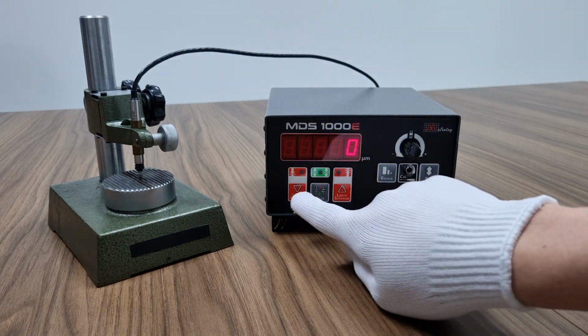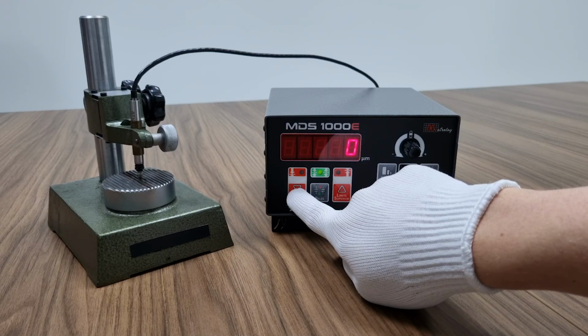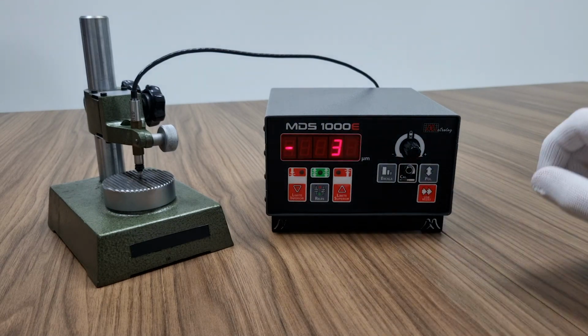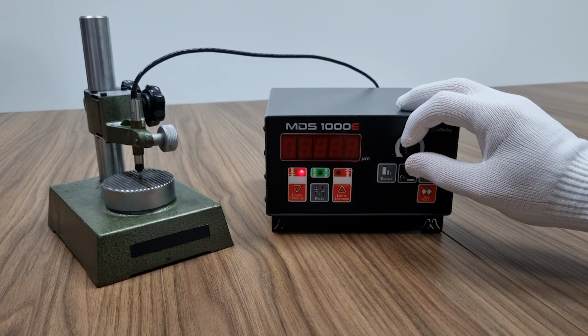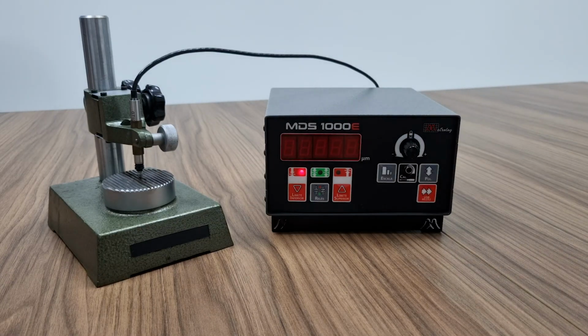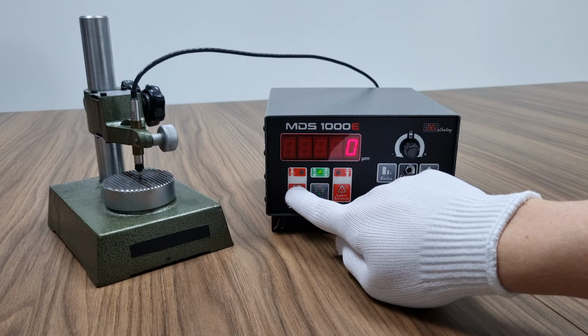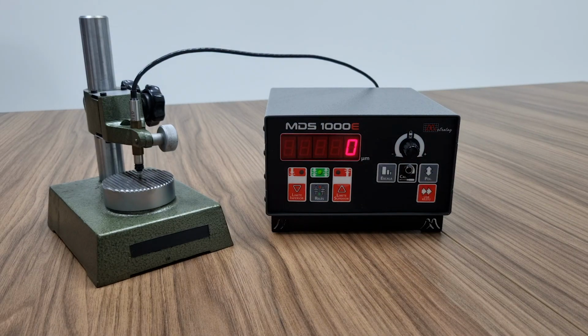The lower control limit must be set by pressing the key for 2 seconds. The value must be changed using the front knob. The instrument will automatically return to measurement after a period of inactivity. The button can be pressed briefly to query the set value.